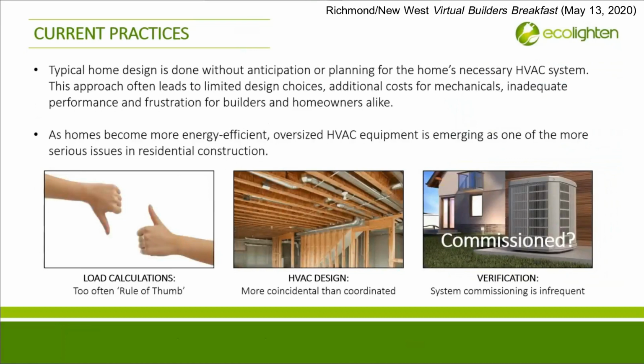How do we approach HVAC systems now? Typically, a home is designed and ready to be built or is in the process of being built. Then a heating contractor will be asked to provide a quote. The heating contractor will provide a quote and a system proposal based on 1, a rule of thumb guess about the sizing requirements, 2, a standardized approach, including preferred equipment, and 3, assumptions about routing and sizing of ducting, grills, registers, and everything else. The quote will rarely include any details about routing, sizing, quality assurance, commissioning, etc. And either a favorite contractor or a lowest quote gets the job.